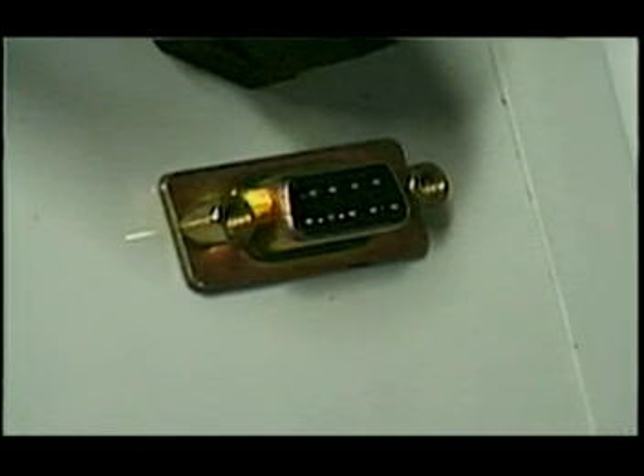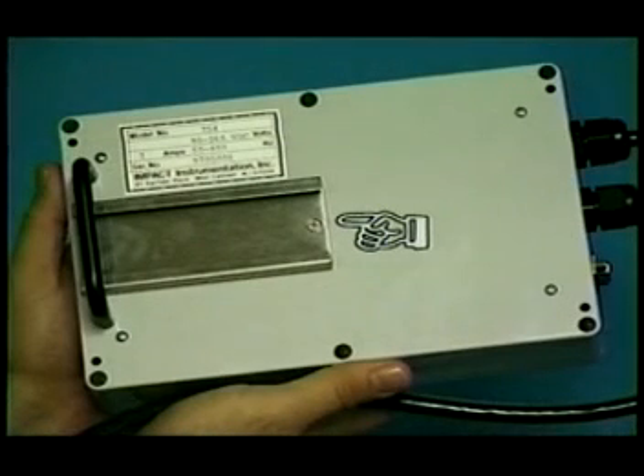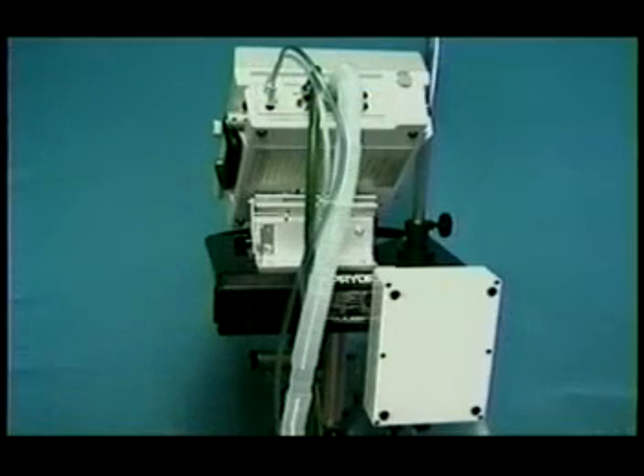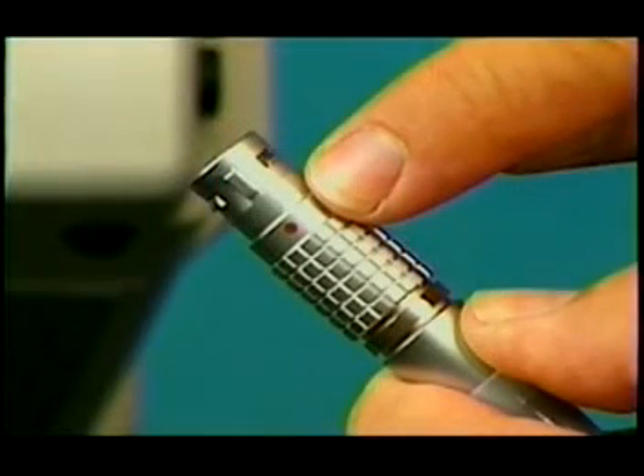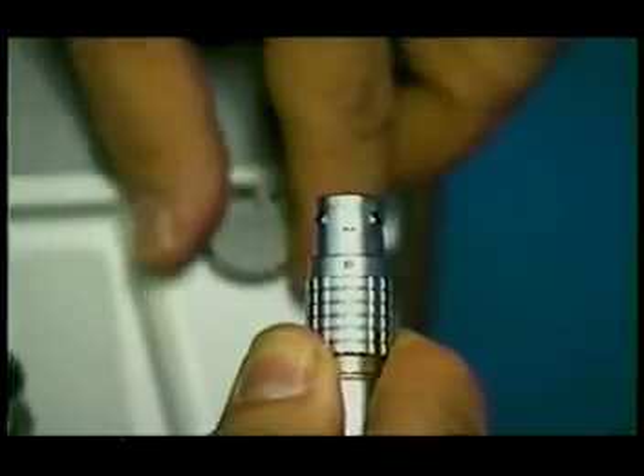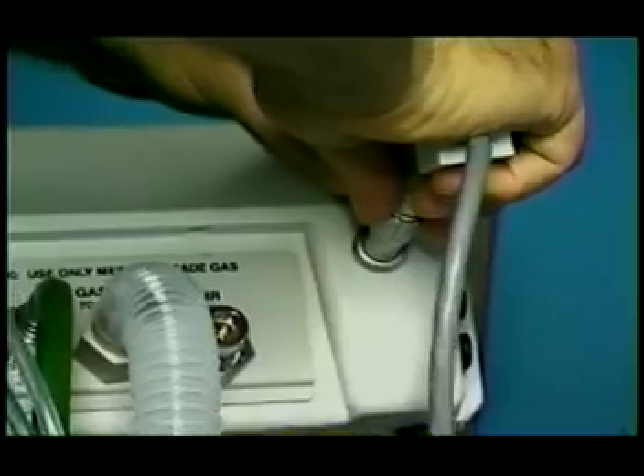The external power supply includes a 9-pin sub-D female RS-232C connector which provides a communications interface for monitoring ventilator switch and control settings, alarms, and pressure signals. A mounting bracket interface on the rear allows attachment to an optional cart, wall mount, pole mount, or the ventilator itself. To electrically connect the external power supply to the ventilator, jack and plug must align to assure correct pin contact. A red dot on the plug aligns to a notch in the jack and allows plug insertion with minimal force.